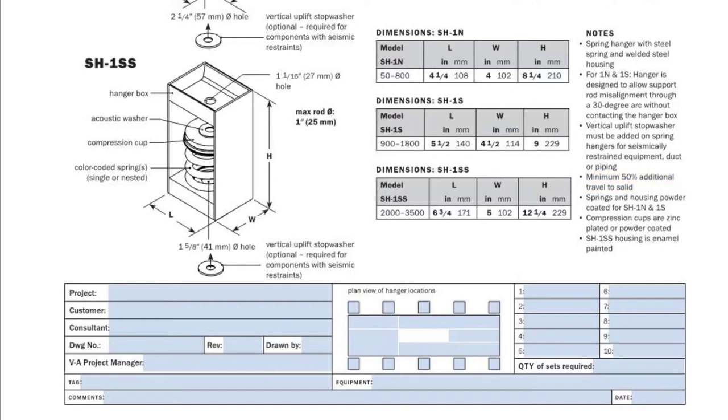On spring hangers supporting equipment or pipe that includes seismic cable restraints there need to be uplift stop washers to help prevent excessive vertical movement. We'll see these again on the installation instructions.